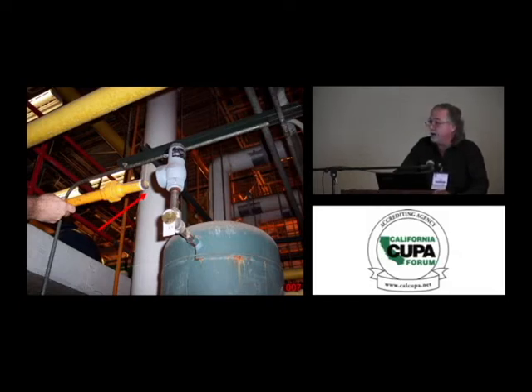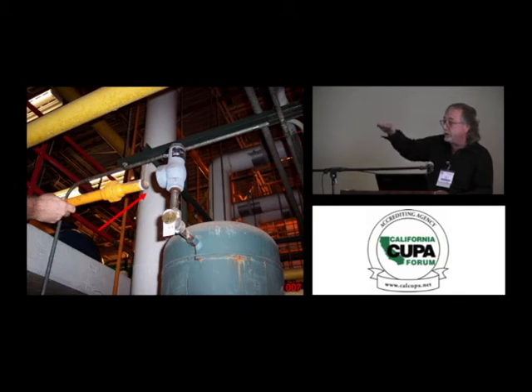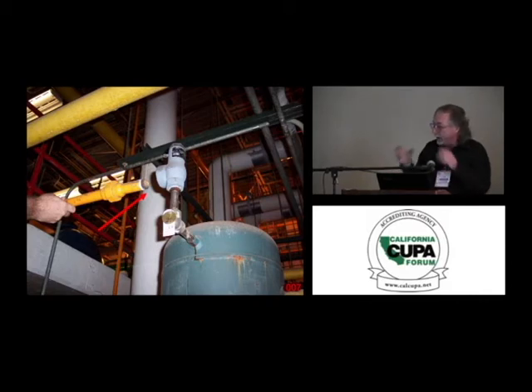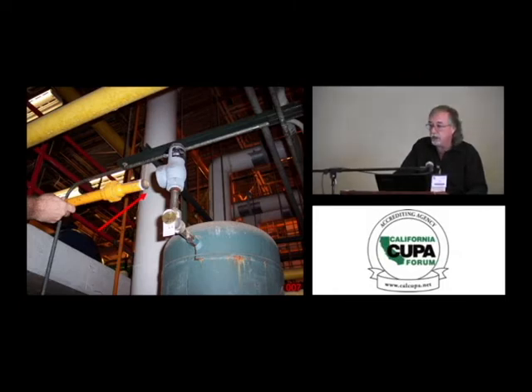We get a high-frequency vibration on screws. Typically, that's because, as Miguel said here, the building's settling. The building starts to settle, the pipes start to hang lower, and they push down, usually the suction line on an ammonia compressor, and that extra weight causes a high-frequency vibration. And those compressors typically will crack lines, crack nipples.